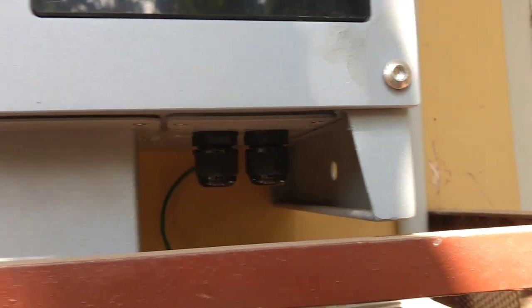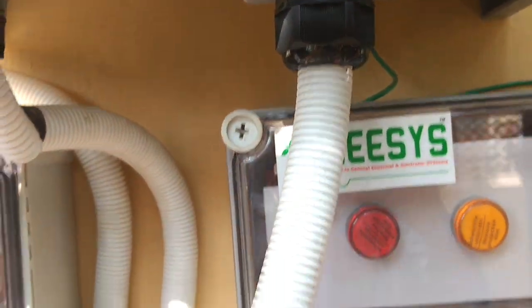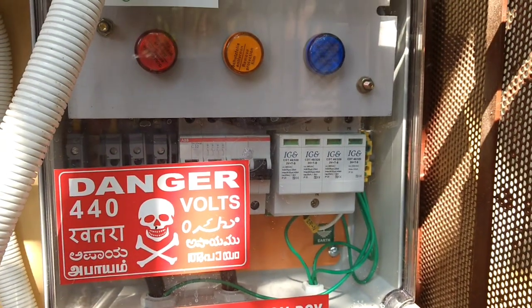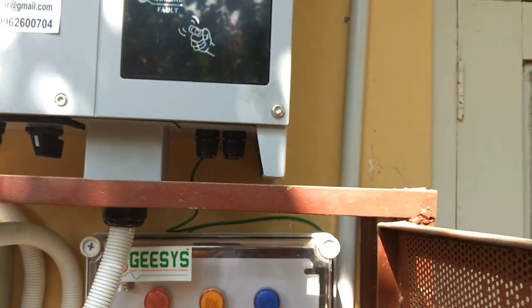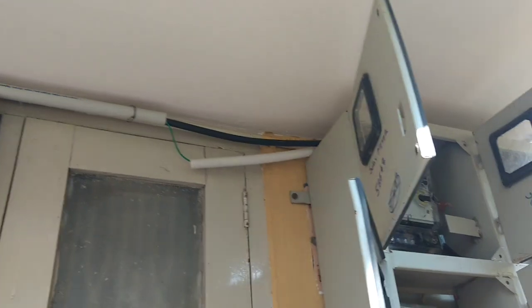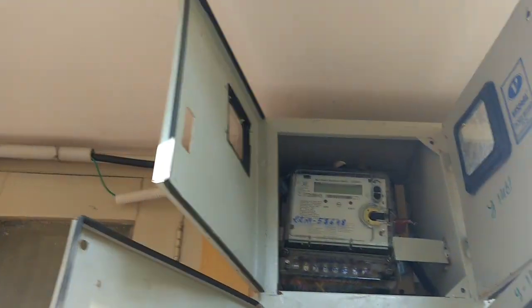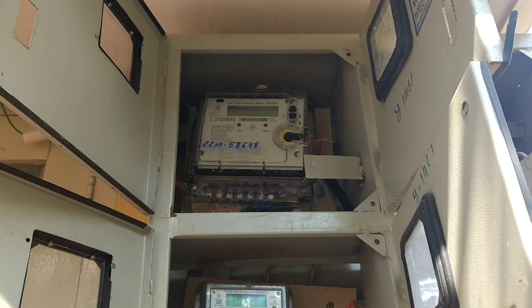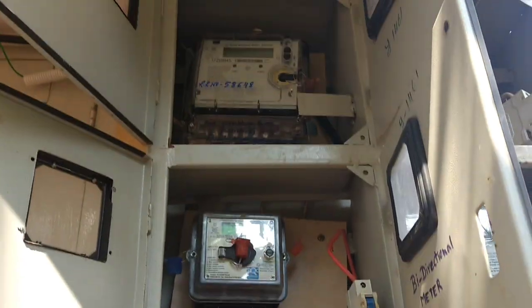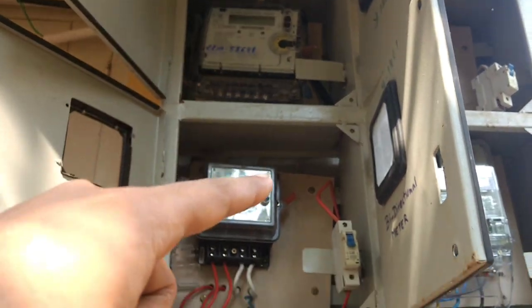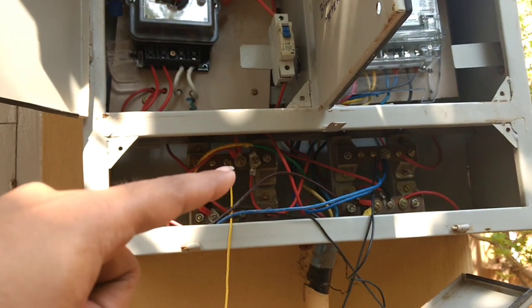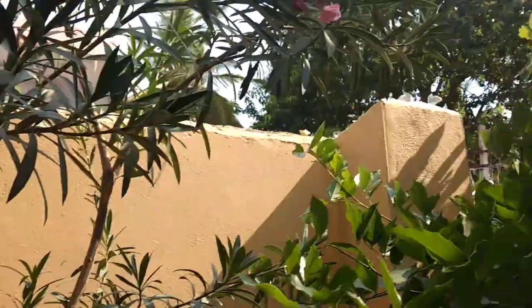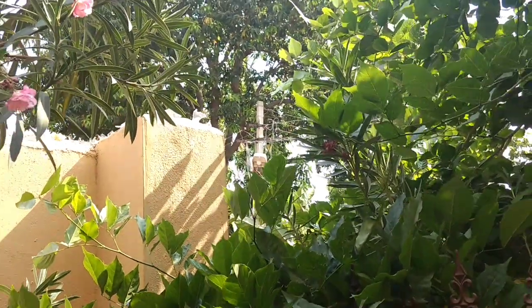When the DC is finally converted into AC, from here the inverter gives the output which goes to an AC distribution box where we have a 63 amp MCB. So from here the wire is going inside that existing meter. Now we have shifted it to the upper left corner. Now it will give you the reading of how much unit of solar output is given, and the output of that meter is directly connected with this bus bar.